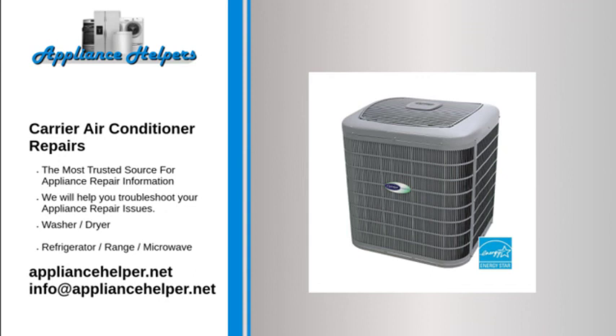Other signs the run capacitor has malfunctioned include slow or delayed startup, system shut down, or the system not blowing cold air. If you suspect a faulty run capacitor as the cause of your air conditioner fan not working, contact a professional HVAC service tech. Capacitors can retain electrical charge and should only be replaced or handled by a licensed and trained professional.